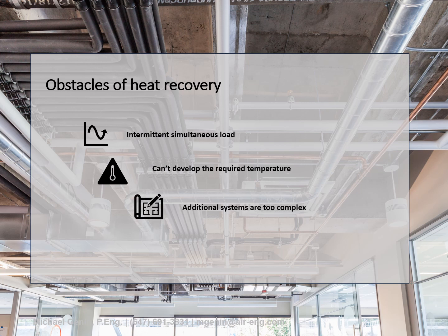These systems sometimes, especially when retrofitted into buildings, require additional equipment, machinery, piping, and systems, and this becomes complicated. And so that generates a lot of apprehension. And lastly, when we implement these physical systems, we also need control sequences to control them. Often these can exist as very simple standalone controls, but sometimes when you integrate with larger building systems, you also need to integrate with a control sequence to ensure that the heat recovery equipment isn't going to fight against some of the existing equipment that's providing heating and cooling to the building in the first place.